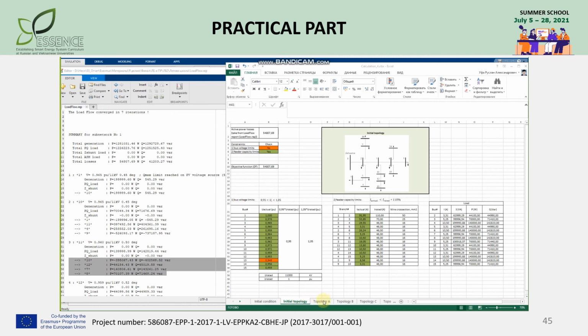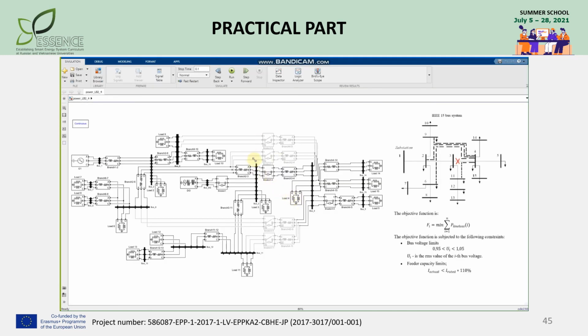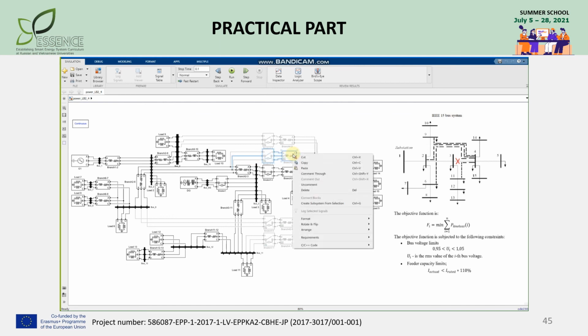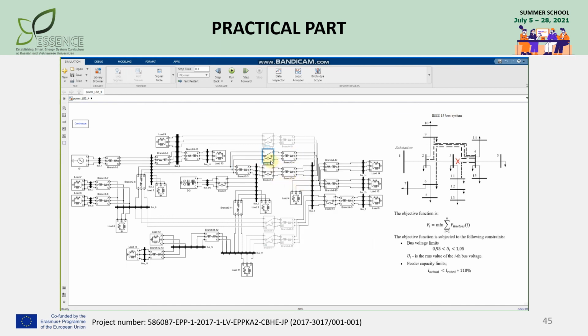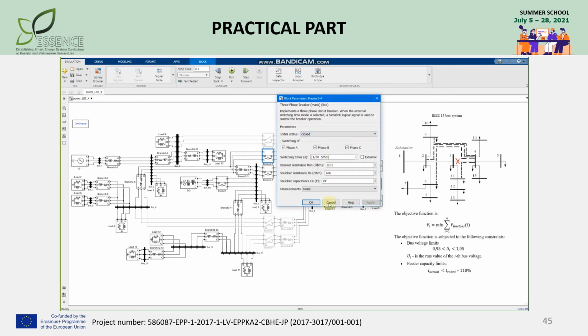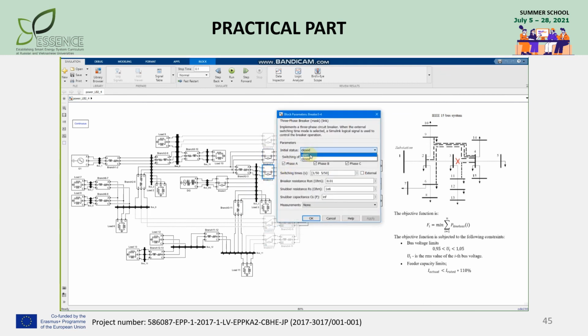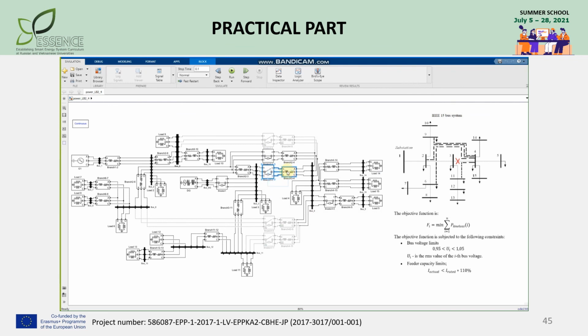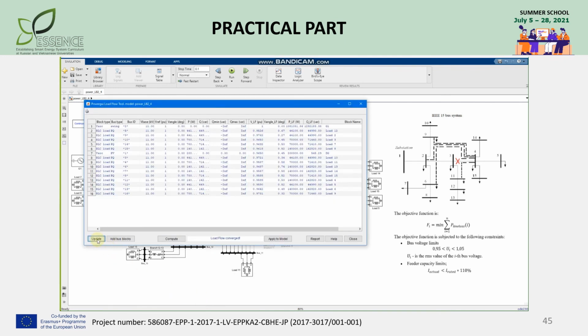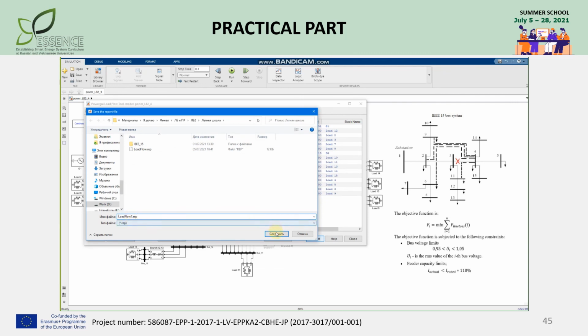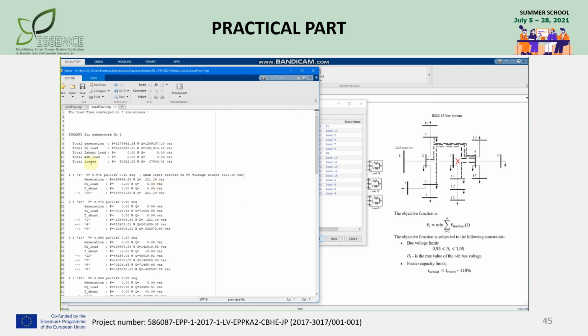The next topology corresponds to the off state of line 3-4 and closed line 2-4. To change topology, we shall command the breakers of line 2-4. Change the status. Then turn off the breakers of line 3-4. Command them. And repeat load flow calculations. Then create the report, save it, and transfer data into the table.